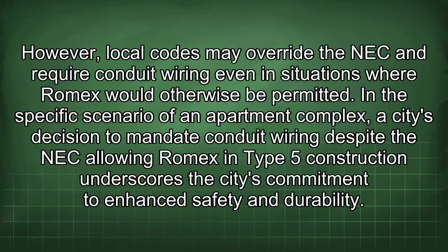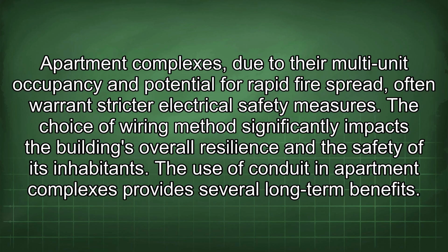In the specific scenario of an apartment complex, a city's decision to mandate conduit wiring despite the NEC allowing Romex in Type 5 construction underscores the city's commitment to enhance safety and durability. Apartment complexes, due to the multi-unit occupancy and potential for rapid fire spread, often warrant stricter electrical safety measures. The choice of wiring method significantly impacts the building's overall resilience and the safety of its inhabitants.